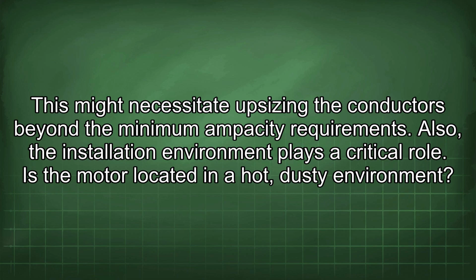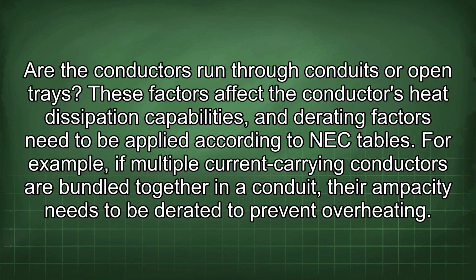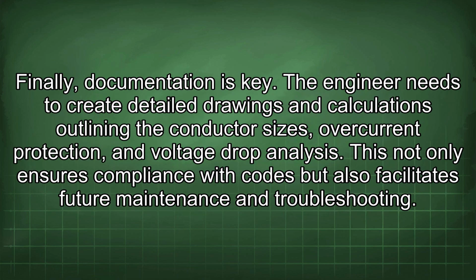Also, the installation environment plays a critical role. Is the motor located in a hot, dusty environment? Are the conductors run through conduits or open trays? These factors affect the conductor's heat dissipation capabilities, and derating factors need to be applied according to NEC tables. For example, if multiple current-carrying conductors are bundled together in a conduit, their ampacity needs to be derated to prevent overheating.